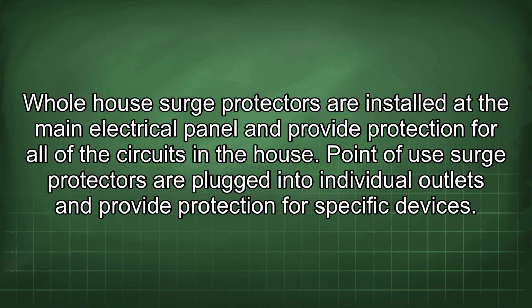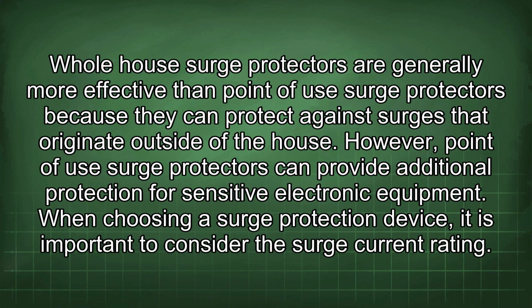There are different types of surge protection devices available, including whole house surge protectors and point of use surge protectors. Whole house surge protectors are installed at the main electrical panel and provide protection for all of the circuits in the house. Point of use surge protectors are plugged into individual outlets and provide protection for specific devices. Whole house surge protectors are generally more effective because they can protect against surges that originate outside of the house. However, point of use surge protectors can provide additional protection for sensitive electronic equipment.